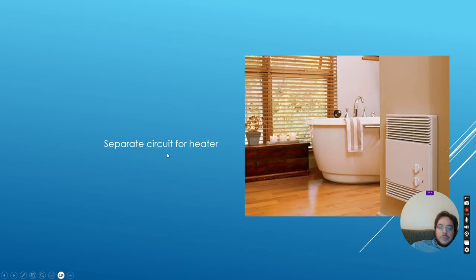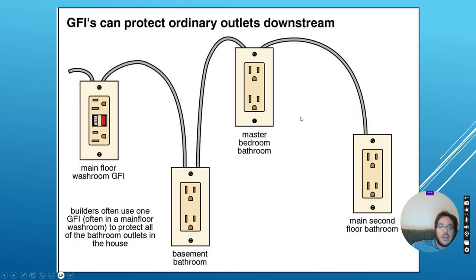Now, the other thing is washroom circuits must be separate from any other circuit. And if you've got a heater in your washroom, then the heater has its own circuit and also GFCI rated. Now, people make this mistake. A lot of times we will daisy chain all of the washroom receptacles, so they will all be on the same circuit.